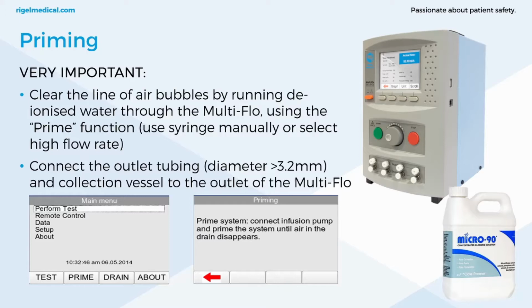So we talk about priming and using the Micro-90 solution. So here we clear the airline bubbles by running deionized water through the Multi-Flo. So many people use deionized water. You can use distilled water, but really we should be mixing a solution of Micro-90 with deionized or distilled water and running that through the Multi-Flo. And the reason for that is that it clears any contamination, any potential for organic growth within the system, and this can have a real effect on the accuracy and performance of the device itself. So we really recommend this. It's not expensive, it's very cheap, it's cleaning solution, and you only need to add a small amount to the fluids.